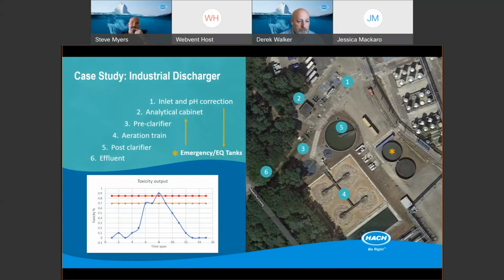In the chart here, you'll see that the EZ7900 influent toxicity analyzer is used to trend that toxicity index over time. This trend line is built every 15 minutes, and they have an early warning alarm set at 70% inhibition. So if they see the respiration rate of the biomass slowing down and it reaches that 70% level, that sends a warning to the operators that they need to keep an eye on that influent.